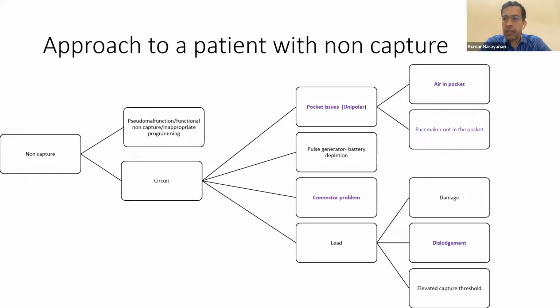Whenever a pacing spike is present, as in your case, the issue of oversensing is ruled out, because if the device was oversensing something, it would not deliver a pacing spike. When you have a pacing spike, you have to look at other issues, such as whether there's an issue with the output, whether it's programming, or whether there's a problem with the integrity of the lead or other connection issues. You have nicely highlighted this systematic approach.